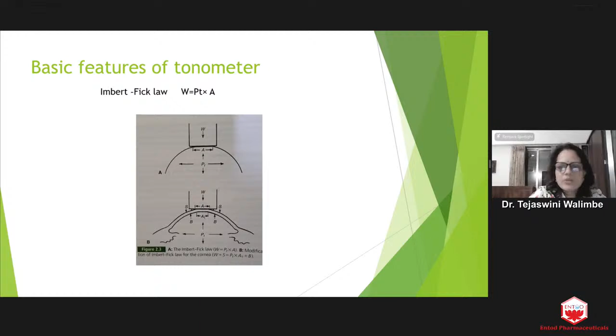Now coming to the technique of the measurement, Goldmann applanation tonometry. First we have to anesthetize the cornea with topical anesthetic eye drops. Then stain the tear film with sodium fluorescein strips which are commercially available, sterile strips. Then illuminate cornea and tonometer biprism with cobalt blue light from slit lamp. And once we have done these things, then we have to adjust the biprism. We should bring the biprism in contact with the apex of the cornea. So here we have to remember that we have to flatten the surface of the cornea. So there is a gentle contact.